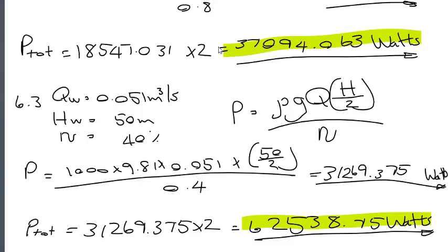Which one uses the least amount of energy? That's obviously the 2 pumps in parallel, which uses 37,000 watts, more or less.